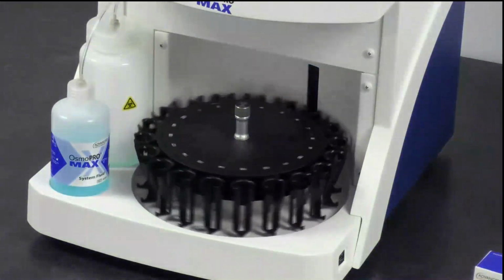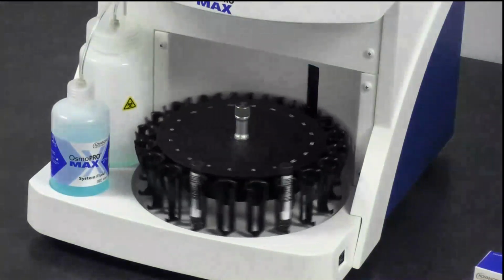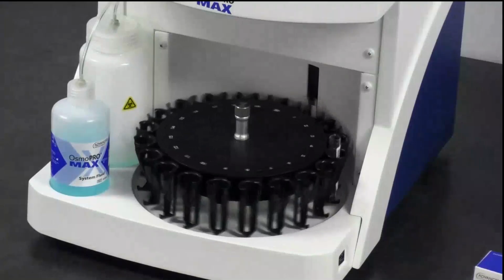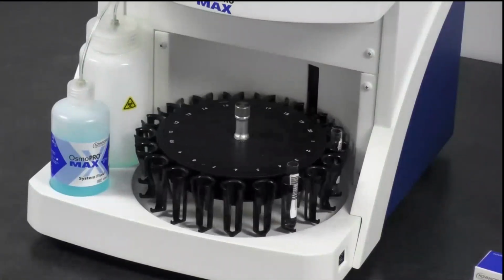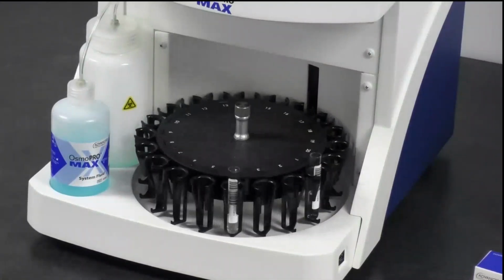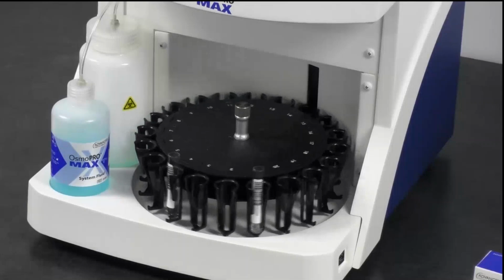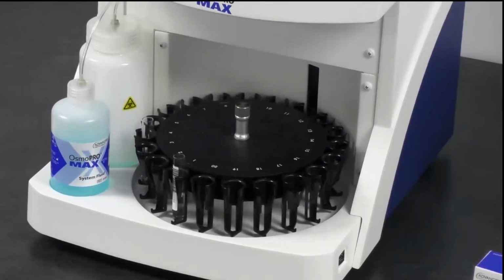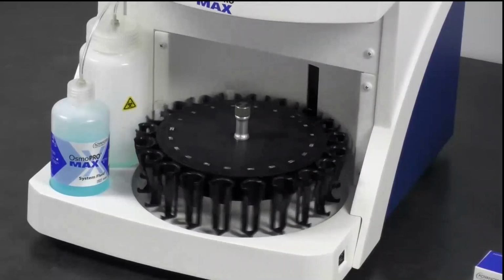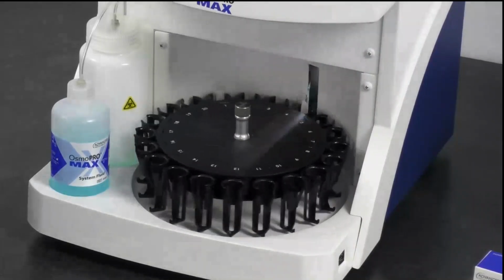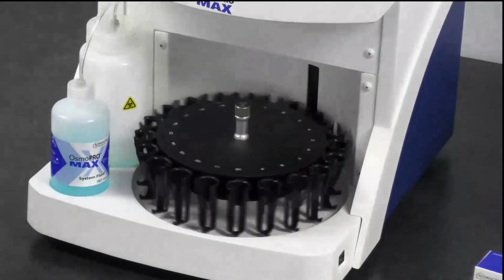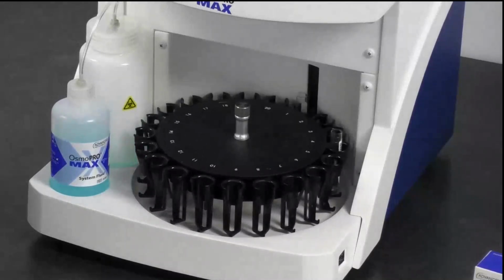And then it's going to go ahead and start doing its thing. So the first thing it's going to do is sense for the presence of tubes in any positions. And then it's going to go through, starting from position 20 and working its way down the turntable, scanning in any positions where it identified tubes were present. So when you see number 4 come through, it's going to scan it. And then number 1's going to come through, and it's going to scan it.